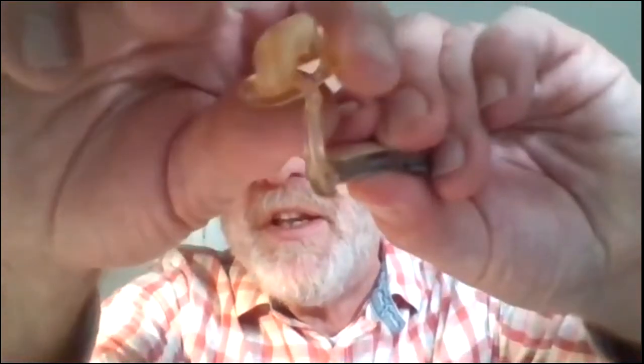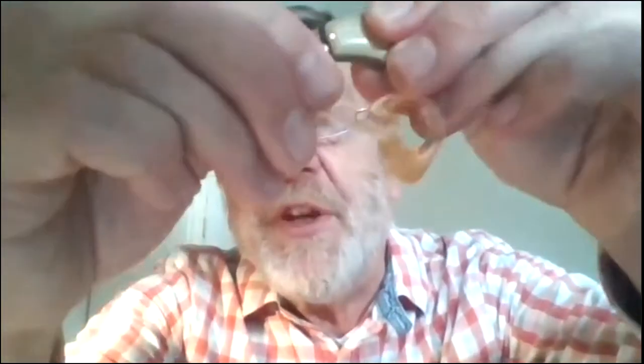Okay, that's feedback. It's sound leaking out of the ear mold and getting picked up by the mic of the hearing aid. And the mic of the hearing aid is that little dot right there underneath the ear hook. See that little dot? If I close the ear hook, now the dot is underneath the ear hook, but the ear hook has a hole. It allows sound to get in, especially when I put my hands around it.